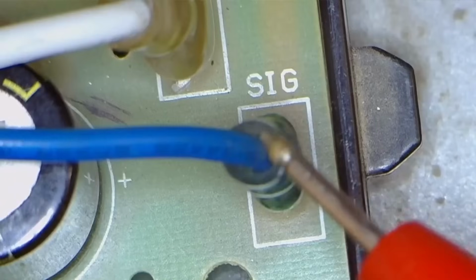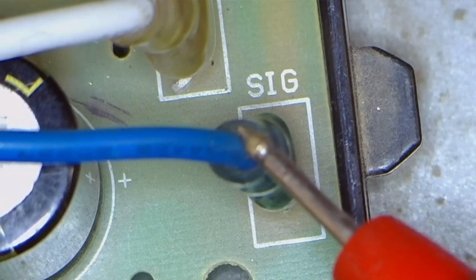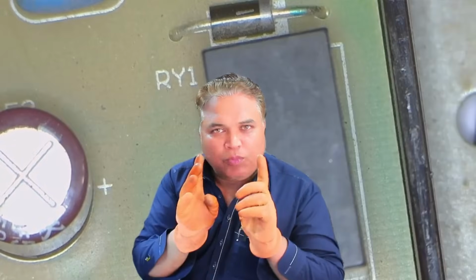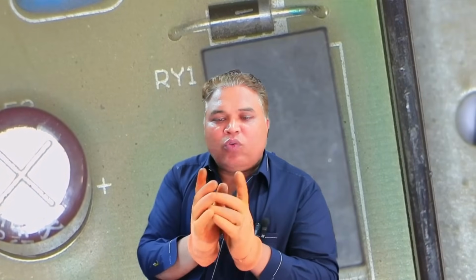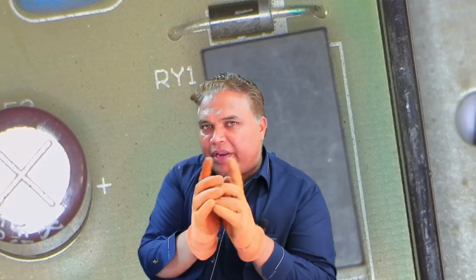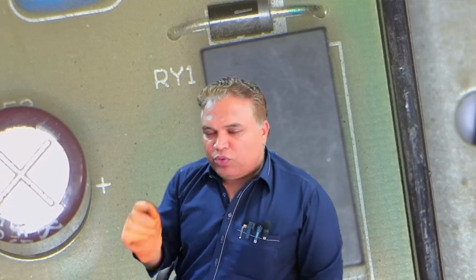However, when we check directly at the signal wire, there is no voltage, meaning the neutral is not reaching there, and this is the fault. The problem lies in the RY1 relay. The relay has developed a fault. Its internal contact points have built up carbon deposits or some damage, due to which they are not connecting properly. As a result, the signal, or the neutral, is not being transferred from the common to the signal wire. This is causing the issue. Now, we will replace this relay and check whether this was indeed the root cause of the problem.